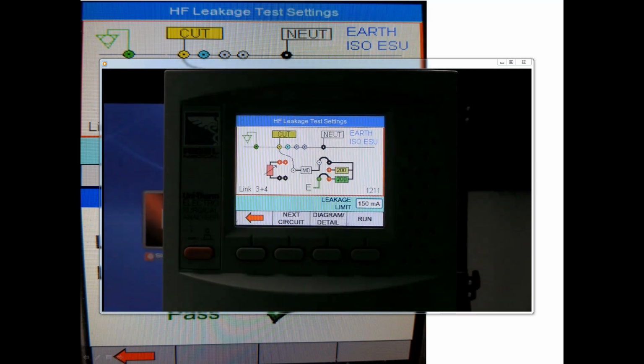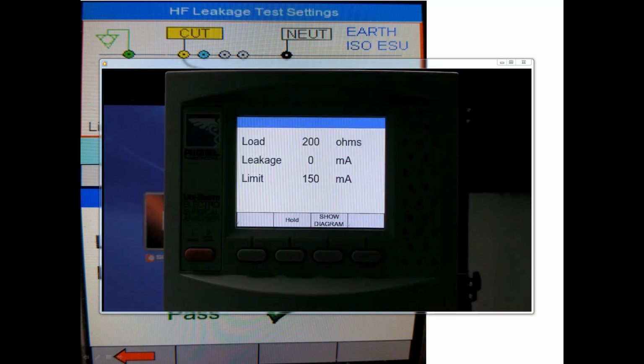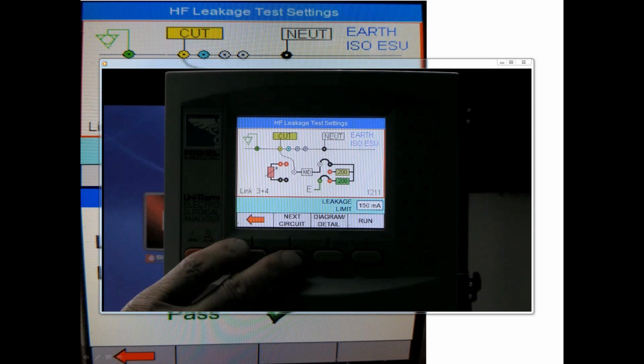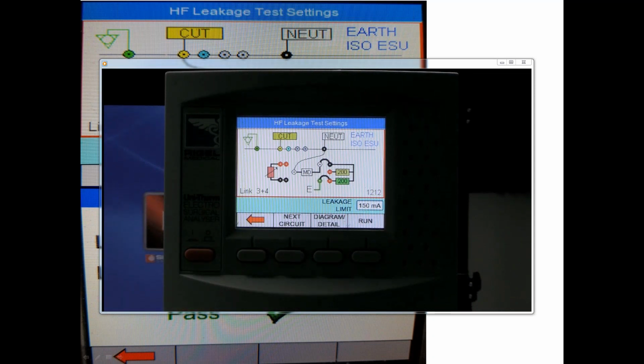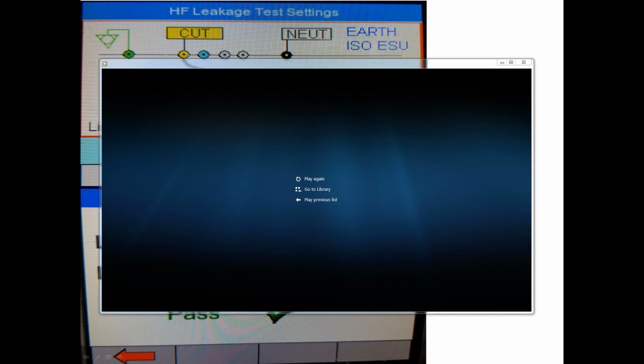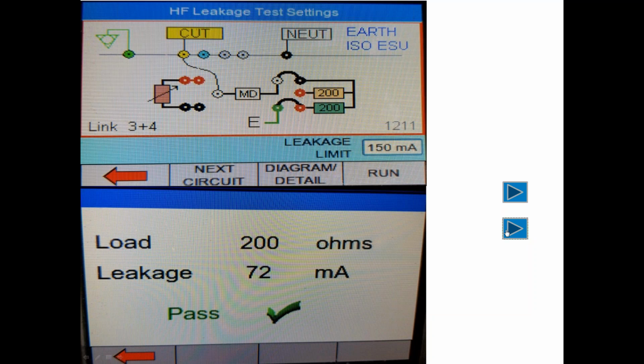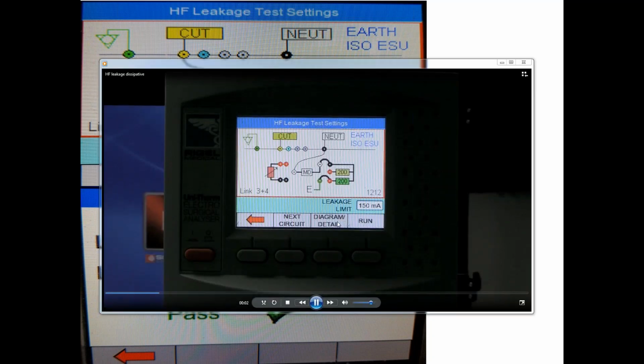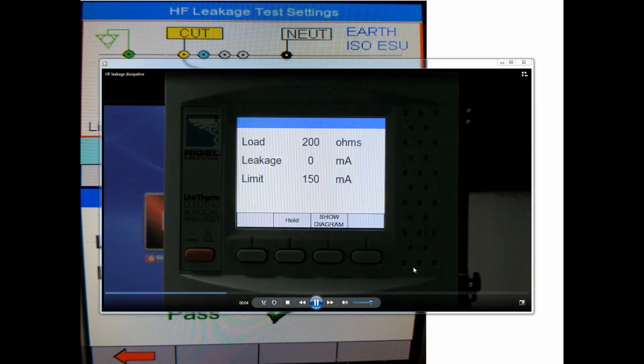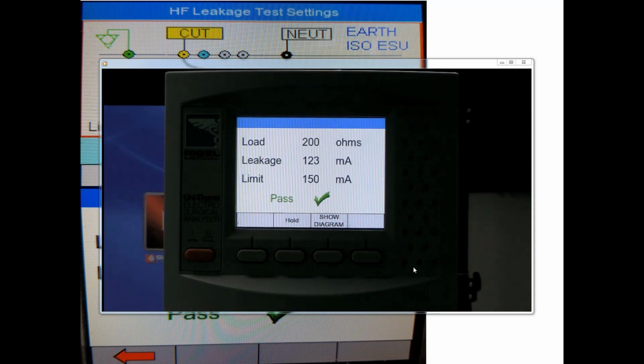There's our test circuit. And there is the leakage current that we captured, 41 milliamps. Now my next circuit, my single fault condition, is going to be an open active. And 123 milliamps is what we measured.